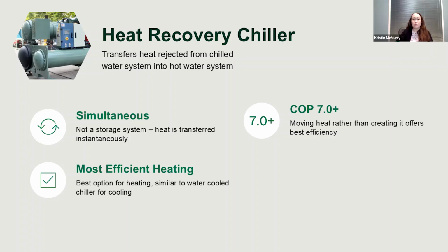Now we have thermal energy from both the cooling side and the heating side, so it makes our COP go up because both of those thermal energies count. Now we have a COP all the way up to 7, keeping in mind that with a plain regular hot water system, we had a COP of 0.76.